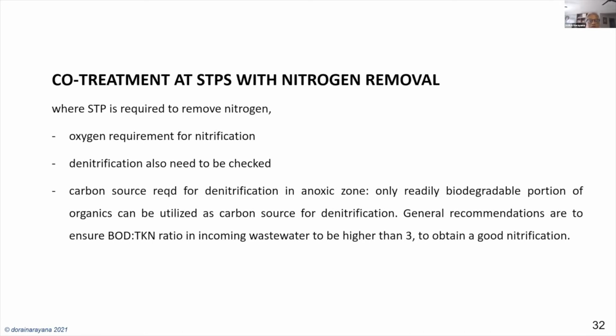When we have nitrogen removal, increasingly many countries have standards for nitrogen or phosphorus removal. And nitrogen removal is done through two processes, nitrification and denitrification. Nitrification requires oxygen, so there will be a take-up of oxygen for that purpose.